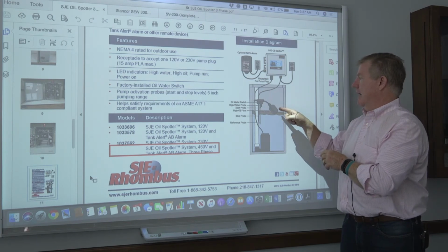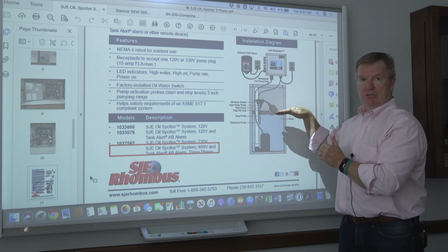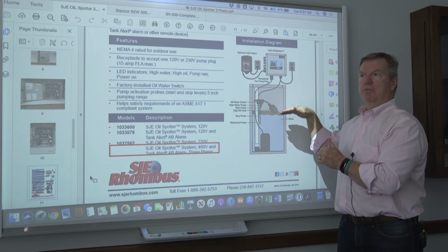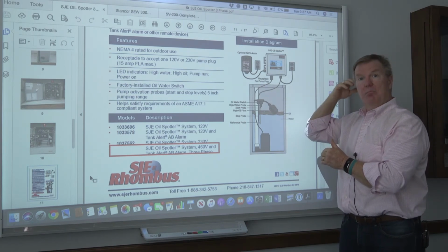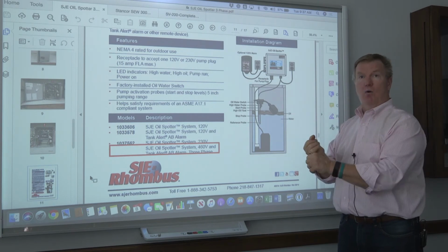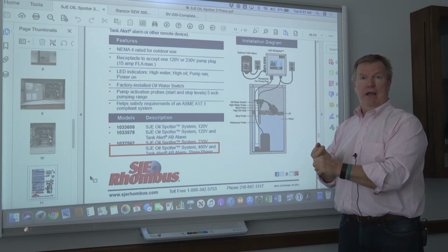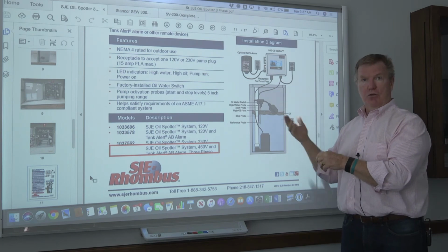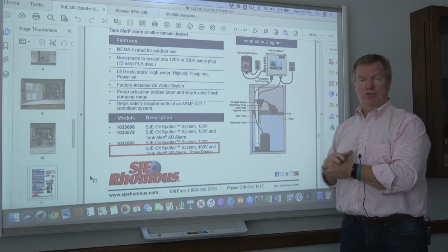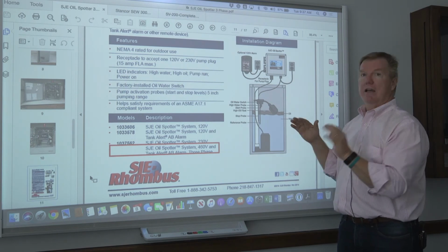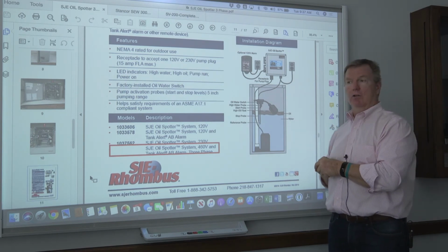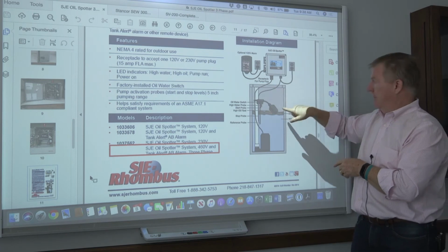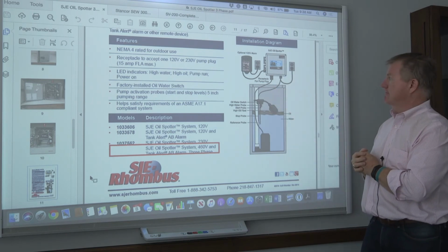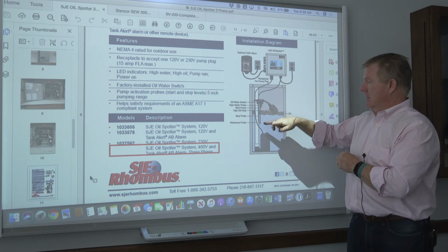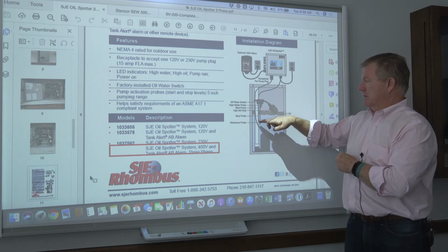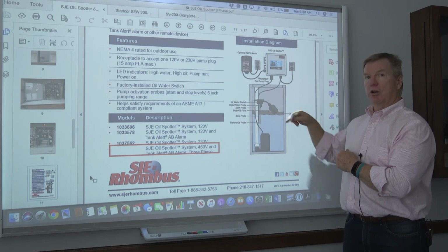So it could be that, if you have a sump pump application where the pit gets high enough that the sump pump doesn't start pumping water out, you'll have a high water alarm first, and then if it continues to go up, you'll also have a high oil level alarm switch that'll give you high oil, even though there may not be any oil in the pit. That's all dependent on that float switch going in the up position. Okay?